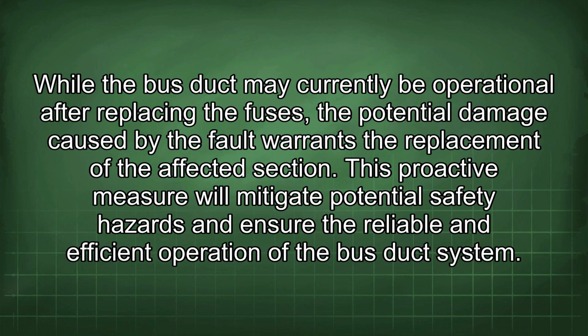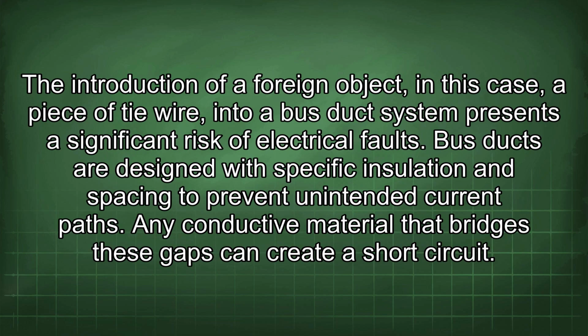While the bus duct may currently be operational after replacing the fuses, the potential damage caused by the fault warrants the replacement of the affected section. This proactive measure will mitigate potential safety hazards and ensure the reliable and efficient operation of the bus duct system. The introduction of a foreign object, in this case a piece of tie wire, into a bus duct system presents a significant risk of electrical faults.